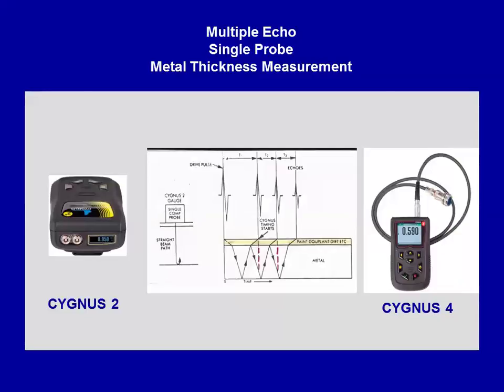When you turn it, especially if you're on a rougher piece of steel, if you're using the twin probe, the geometry of the V is changing as you turn it around. And as that's changing, so do the numbers on the gauge. So the question always was, and I would go to shows and go to my competitors, because they always had nice shiny steel out on their tables, where we always bring the crap. Because that's the world we live in: crappy, corroded steel, not nice shiny test blocks.